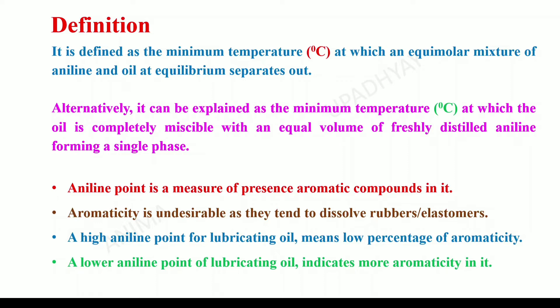Aniline point is important because it gives us information about the presence of aromatic compounds dissolved in the given lubricating oil. If the aniline point is high, it states that the aromaticity present in the lubricating oil is low. But if the aniline point is low, it suggests that the aromaticity in the given oil is high, and high aromaticity is undesirable. So a lubricating oil with a low aniline point is not recommended for machines having parts made up of rubber or elastomers.